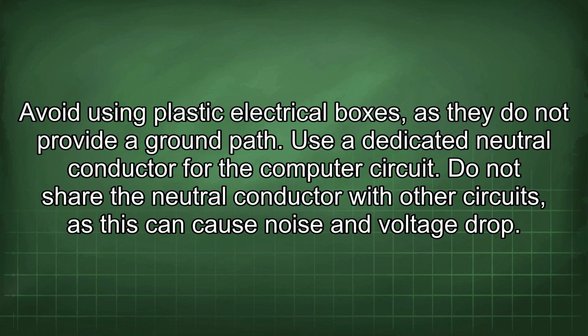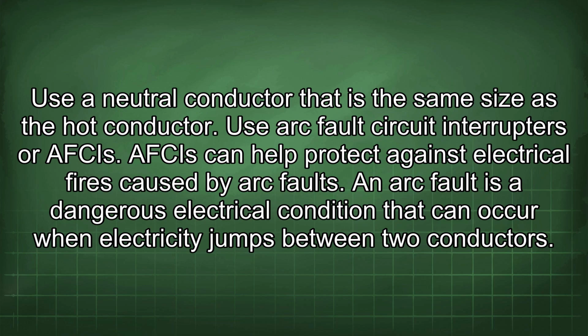Use a dedicated neutral conductor for the computer circuit. Do not share the neutral conductor with other circuits, as this can cause noise and voltage drop. Use a neutral conductor that is the same size as the hot conductor.